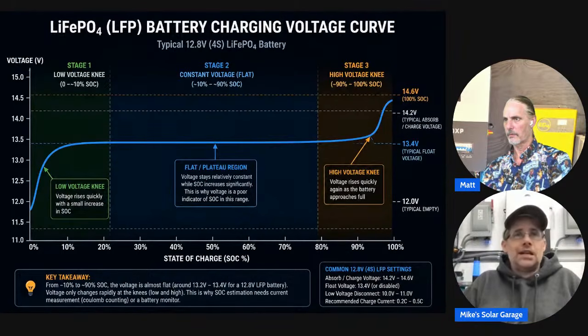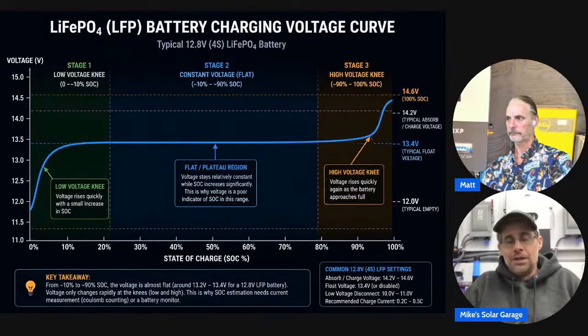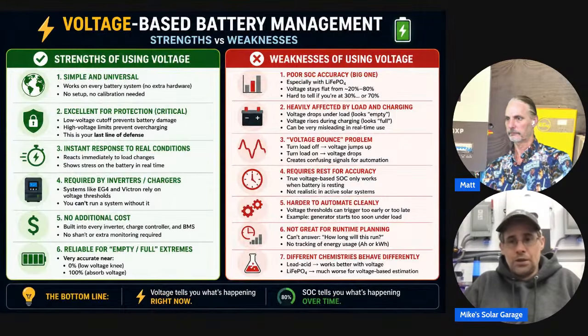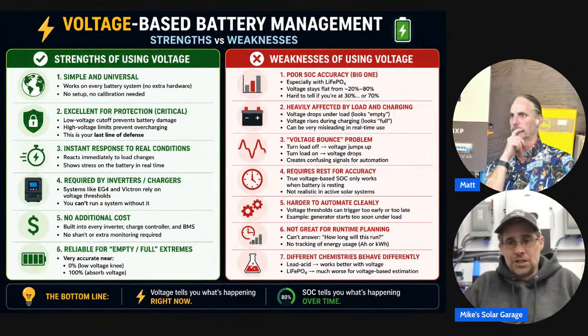You also have to take that with a grain of salt, because it also depends on the load on the batteries at that time - is there a voltage drop or not, because that plays into it. Also, if your batteries are charging, that's going to be a different voltage, because you're getting that fake reading, if you will, since the solar is assisting and charging it, so it shows a higher voltage. The moment you stop charging and give the batteries time to settle, that voltage will settle down to what the battery's actual capacity is at that state.